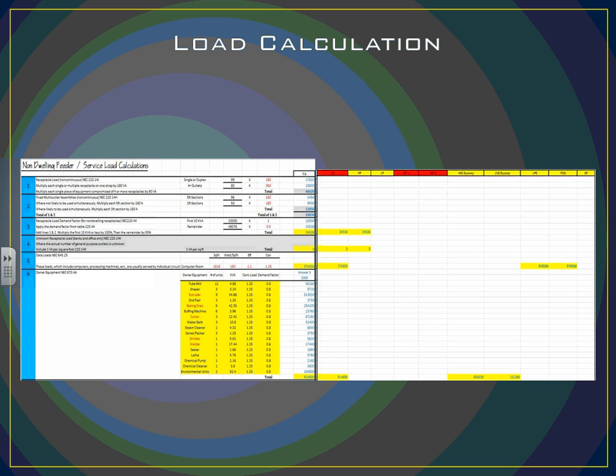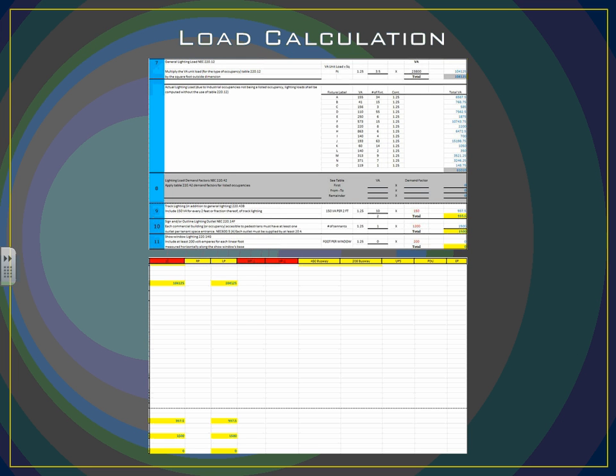So running through some of those, we were able to plug in the information based off of how many pieces of equipment we had, KVA ratings, and then the demand factors, so power factor and everything that we had for those. So we plug in that information. Down the list from there, we used it for lighting calculation also, which is based on the same format. We have the fixture labels. We use KVA and a continuous load 1.25 calculation, and then let that calculation drop through. So you'll see here it goes to the switchgear, KVA for the lighting panels, very similar all the way down.